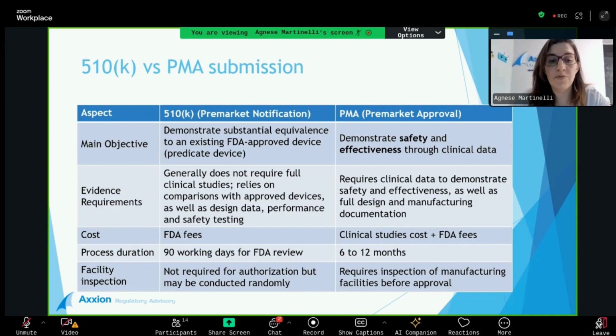And also, if we take a look at the process duration, the 510K is shorter. It lasts 90 working days for an FDA review, and it can go up to 12 months in the case of PMA. Regarding the facility inspection, we mentioned that only the PMA requires the manufacturing inspection of the facilities just before the approval. In the 510K submission, it is not required before the product is cleared, though we know we can be randomly inspected by the FDA at any point.